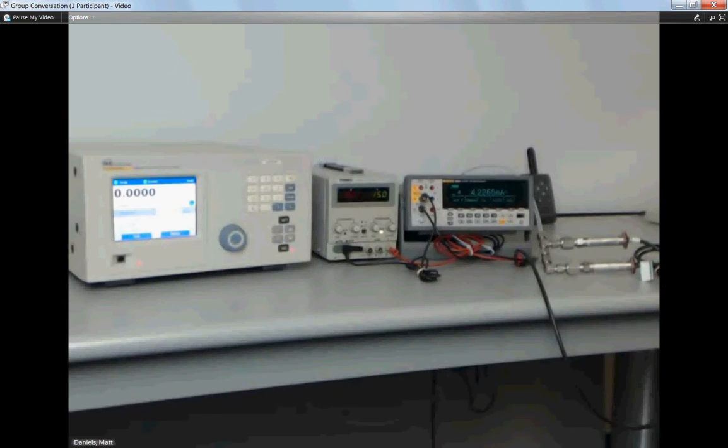The pressure sensors are off to the right. There's two of them. We're only going to be calibrating one of them in this example, but the output is being read by the Fluke 8846A digital multimeter, and we have a benchtop grade power supply providing the current loop. And the reference pressure is coming from the Fluke Calibration model PPC4.